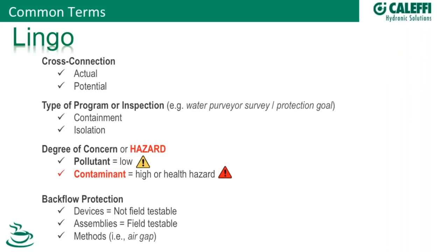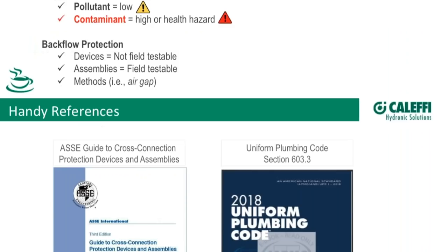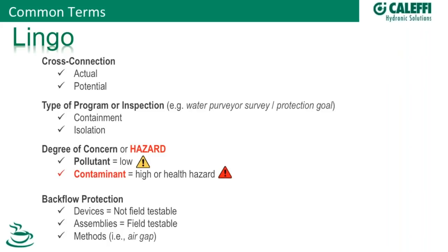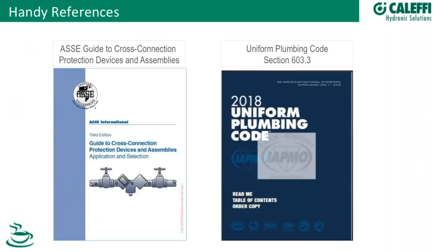Is it going to give you a little stomach ache and make you a little bit ill, or have an objectionable odor, appearance, color, or taste? Contaminant — now that's something that could really put you in the hospital or could be fatal. So that's where we have to delve into very serious backflow protection. Devices are typically associated with low hazard. Assemblies are associated with high hazard or contaminant. Methods would be air gap — your best level of protection, atmospheric or air separation between safe potable water and a suspect source — but not always practical. You can't always have an air gap because you might need your system pressurized or you might need the chlorine to stay in the state it's being delivered.